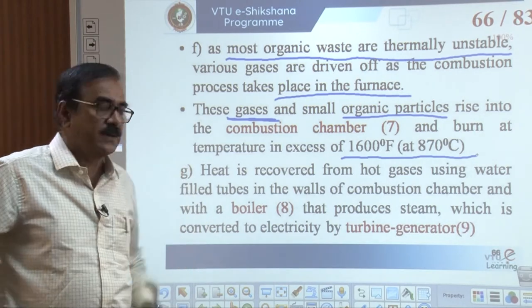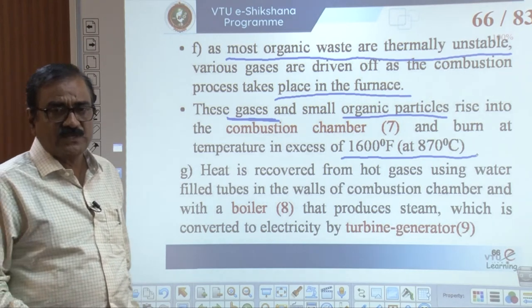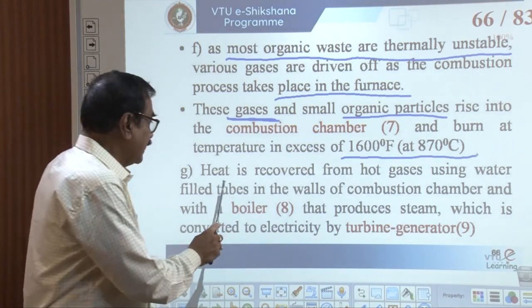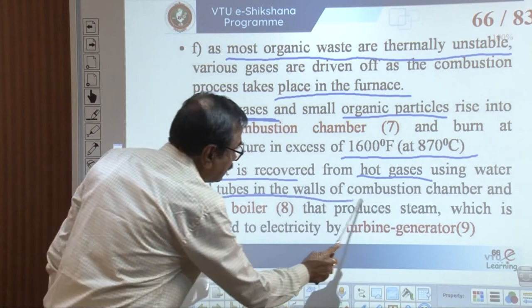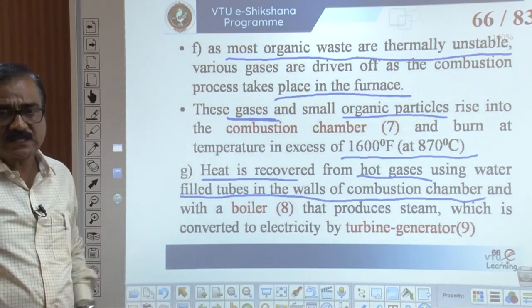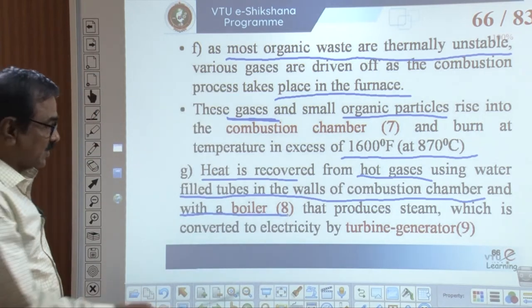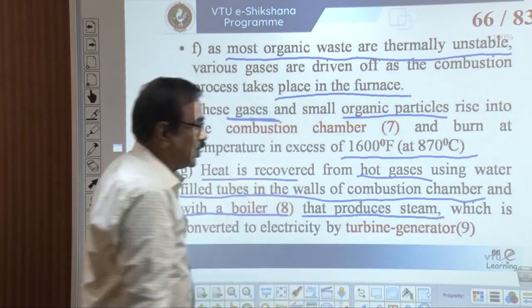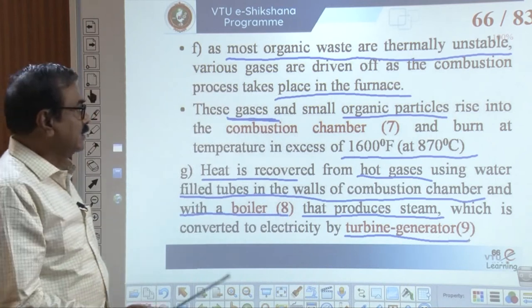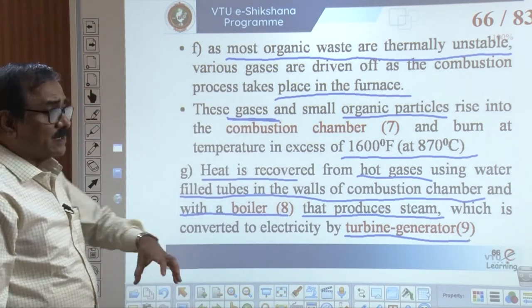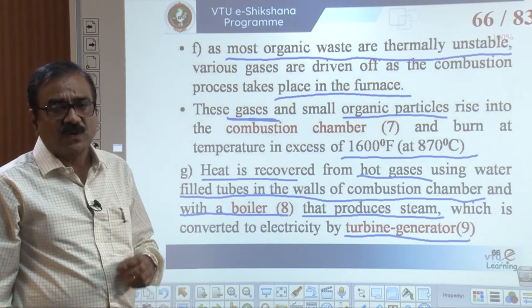Around 900 degrees Celsius temperature is necessary for effective burning of the commingled municipal solid waste. Now with burning complete, another important objective of the incineration process is energy recovery. Heat is recovered from the hot gases using water-filled tubes in the walls of the combustion chamber — a boiler arrangement — which produces hot steam that is finally converted into electricity by a turbine-generator.